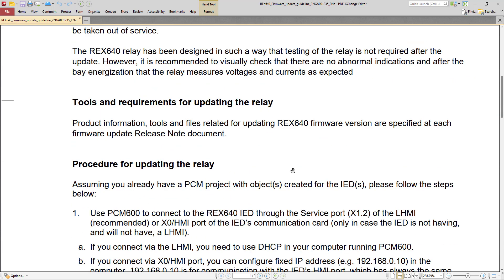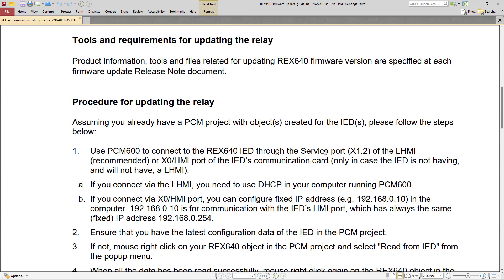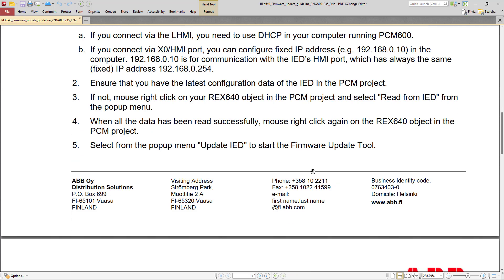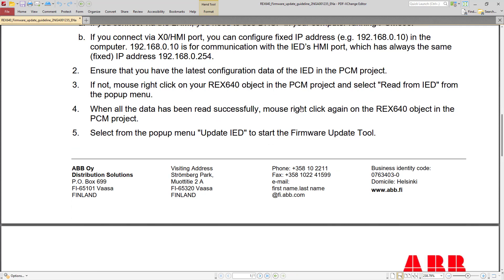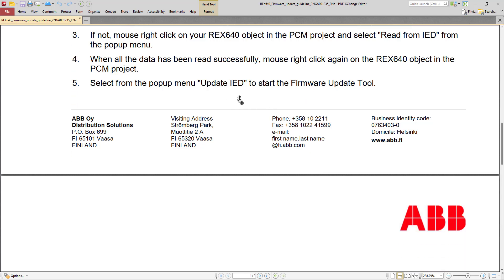It's a simple step-by-step process. I have connected my PCM600 installed PC to the network. There is a service port on the back of the REX640 that can be used for firmware update. You can connect directly if you have one IED; if you have many IEDs in a substation, you can do it from the station bus. You can also use different access points like X1.2 and X0, and the HMI port can be used as well. It's also highly recommended to add the IED into PCM600 and perform a read from IED operation to collect all configuration information before updating. Then right-click the IED and use the Update IED option.